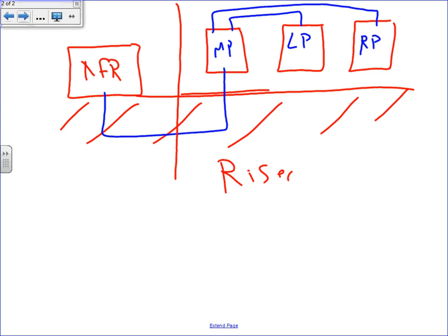And we're going to add more to the riser. But as of now, what you did with me is we have a transformer sitting outside. We didn't size it yet. That's Excel's job. We brought the power to the building to a panel we call a main panel. From the panel, we went underground. This area is out. When we got inside the building, we went above ground. 99% of the time, if you're under the building, you're using PVC. When you're over here, conduit-wise, you're using EMT, 99% of the time. Okay, so that's your riser.